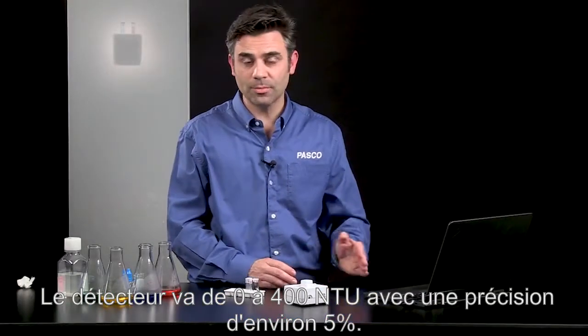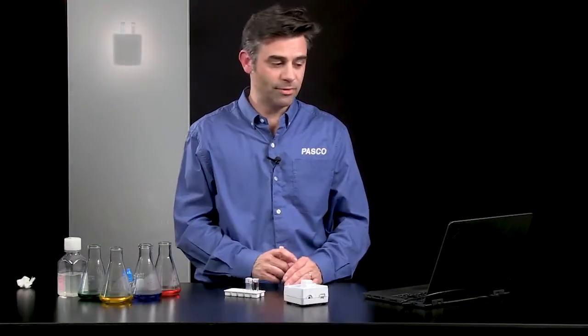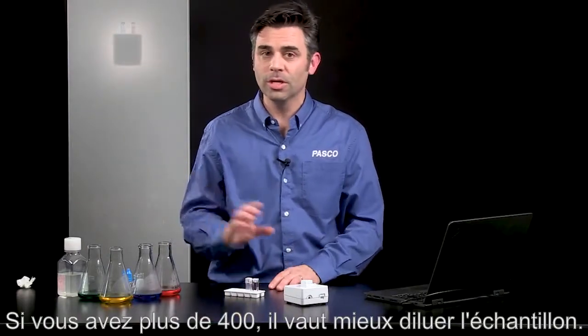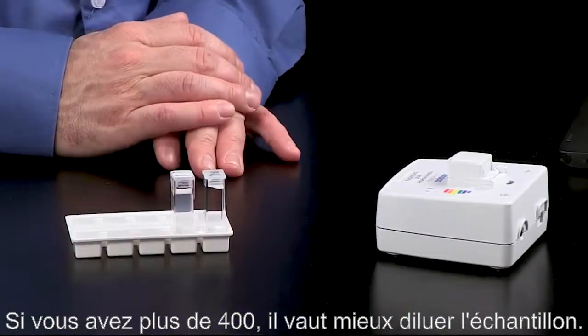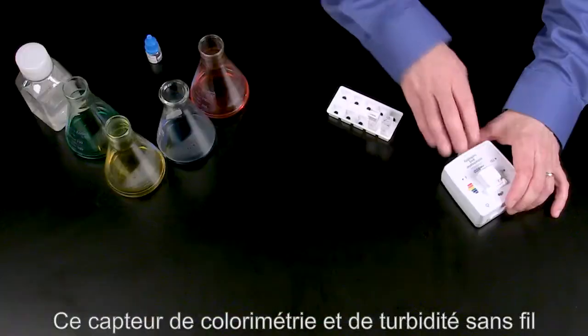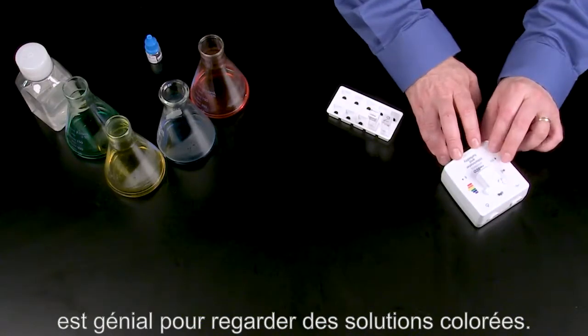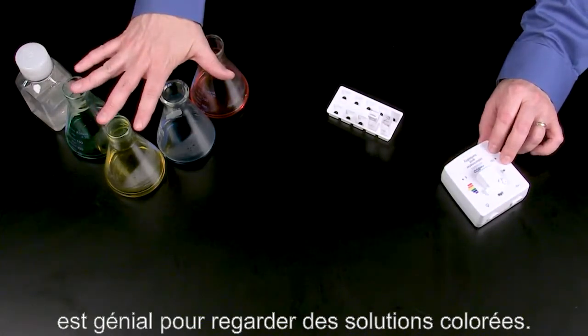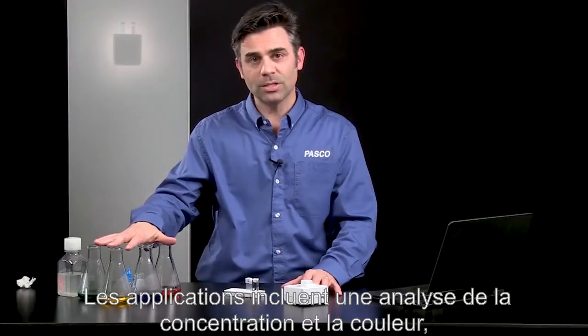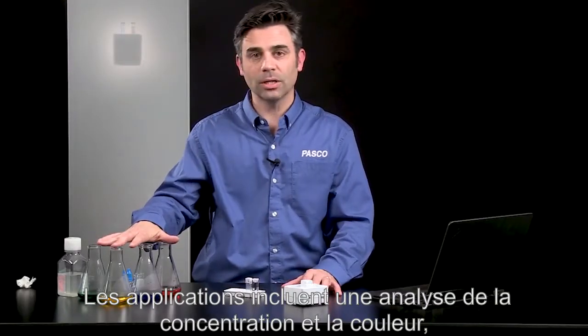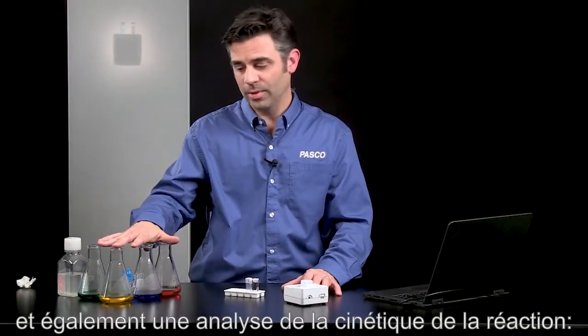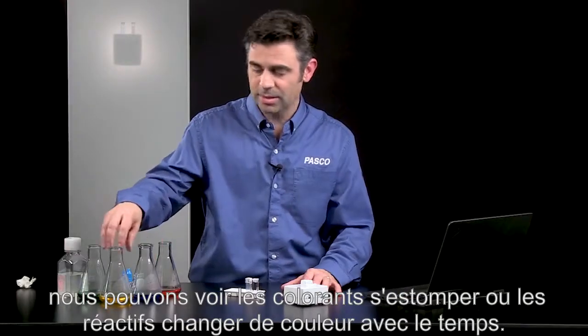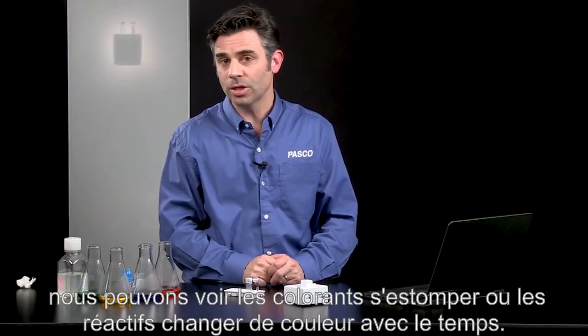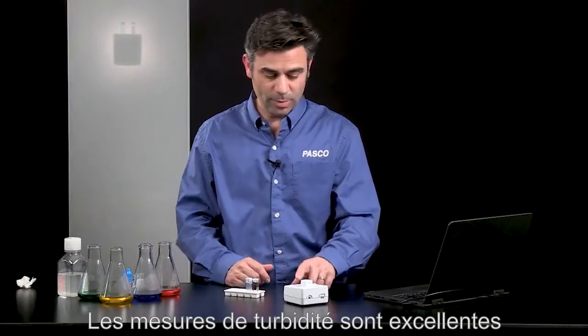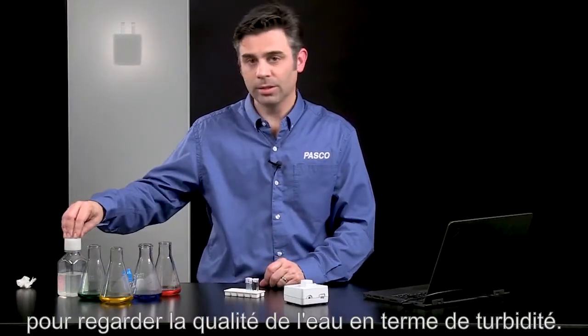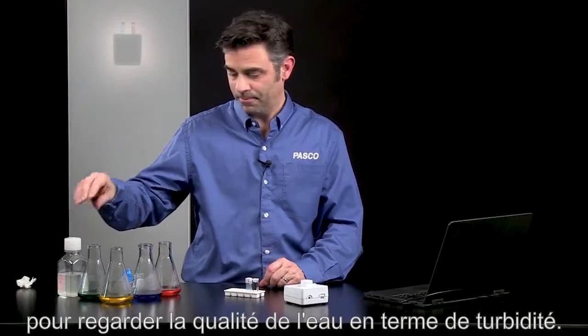The detector range is from 0 to 400 NTUs with an accuracy of about 5%. So if you are over 400, you will want to dilute your sample. And so this wireless colorimeter and turbidity sensor is great for looking at colored solutions. Applications include looking at concentration and color, and also looking at reaction kinetics, so we can see dyes fading or reactants change in color over time. And the turbidity measurements are great for looking at the quality of water in terms of turbidity.